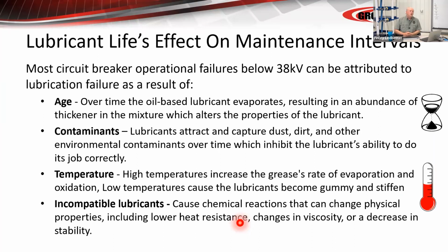Okay, we're doing good. The life effects of lubricants are very important: age, contaminants, temperature, and incompatible lubricants. Those are the four big killers. So be careful spraying anything, replacing anything, or allowing a contractor to bring any lubricant and inject it into your mechanical systems if they don't know what they're doing and you're not sure it's correct.